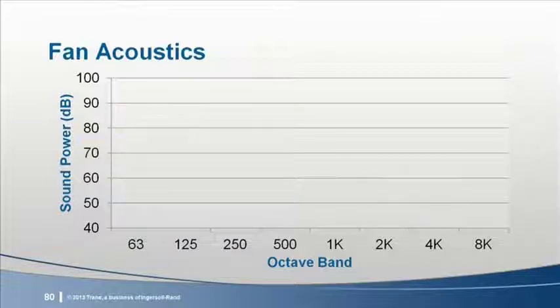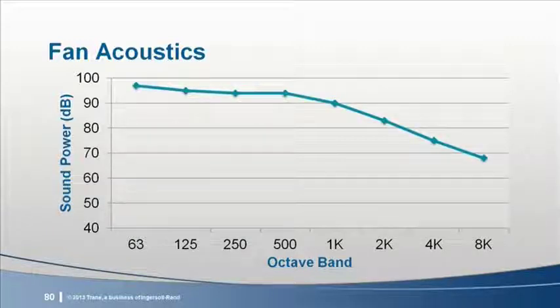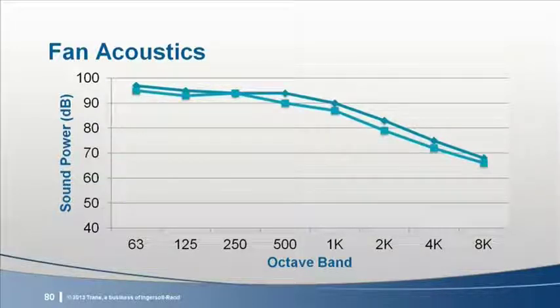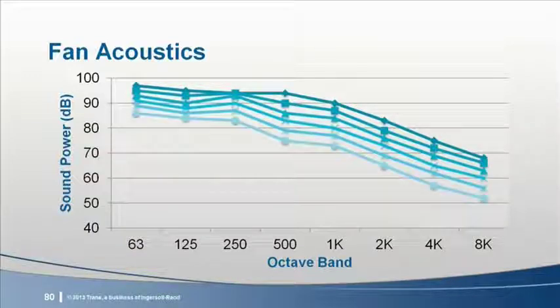The primary octave bands are shown across the horizontal axis, and the sound power level, measured in decibels, is shown in the vertical axis. As the fan operates at design airflow, sound is generated at each octave band. When the fan begins to turn down to 90% of design airflow, the sound power decreases. As the fan turns down further, the sound levels will continue to decrease, shown here in 10% intervals. The sound generated is based upon the type of fan, flow rate, total pressure, fan efficiency, drive system, and discharge.